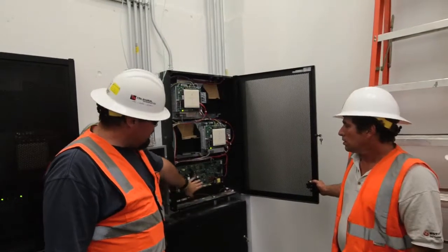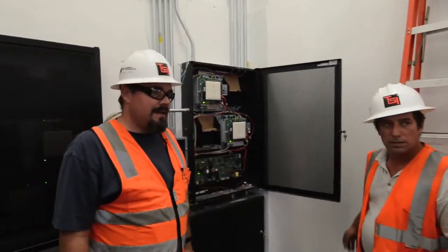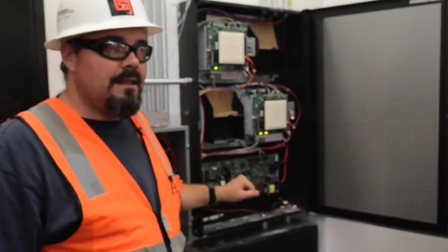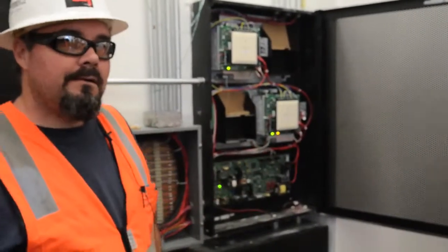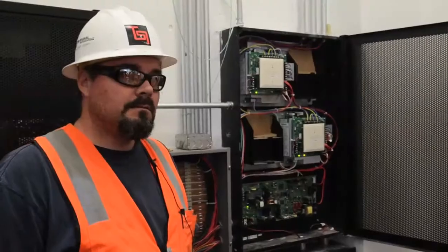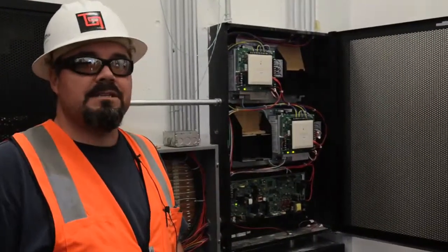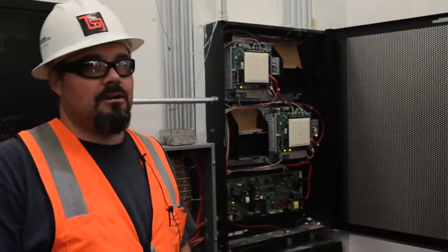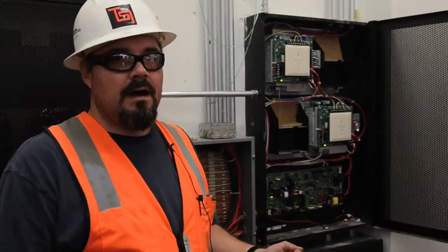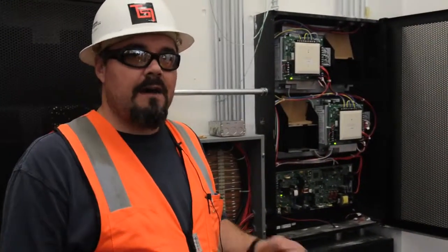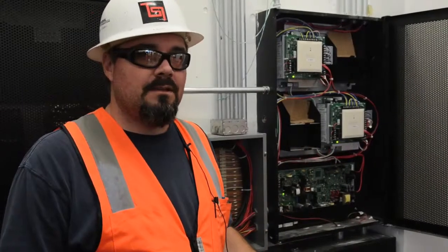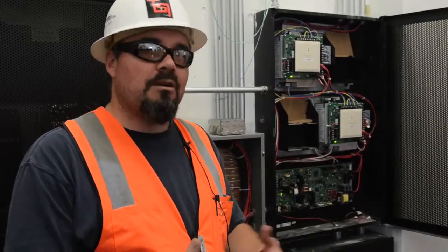And then this right here is our amp for the voice evac. So we have 3 voice evac amps. That's what I was wondering, is the voice independent of the regular paging system that I saw? Yes, it's independent, but we're setting up the PA also to have alarms, and they will be connected together. So the fire alarm goes off, it will cut off any PA working at the time and just be the fire alarm announcement. So they are going to be networked together.